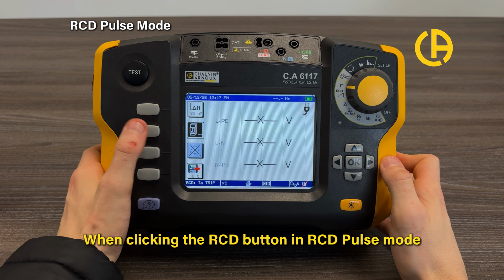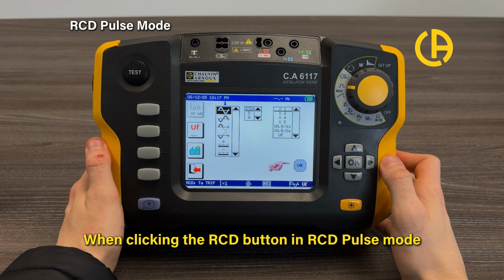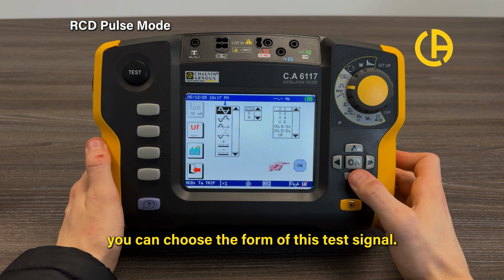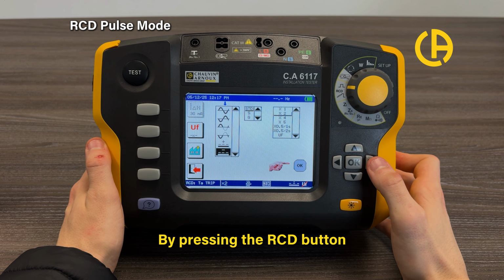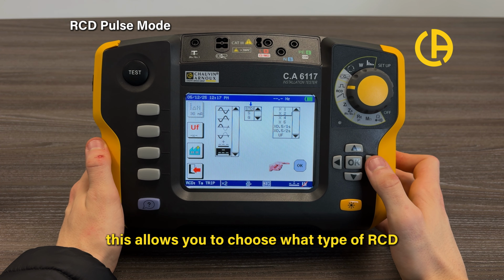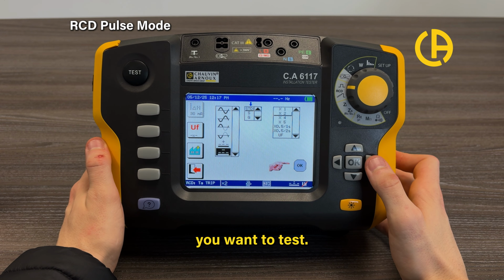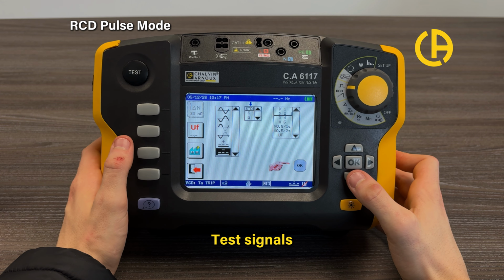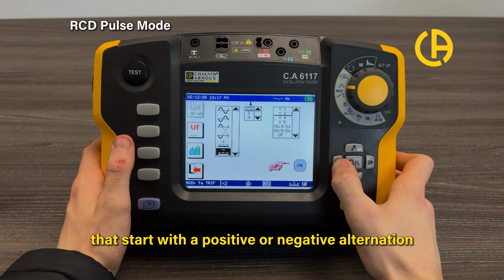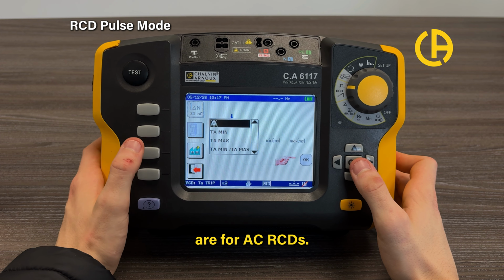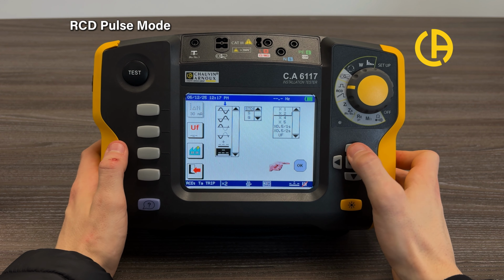When clicking the RCD button in RCD pulse mode, you can choose the form of this test signal. By pressing the RCD button, this allows you to choose what type of RCD you want to test. Test signals that start with a positive or negative alternation are for AC RCDs.